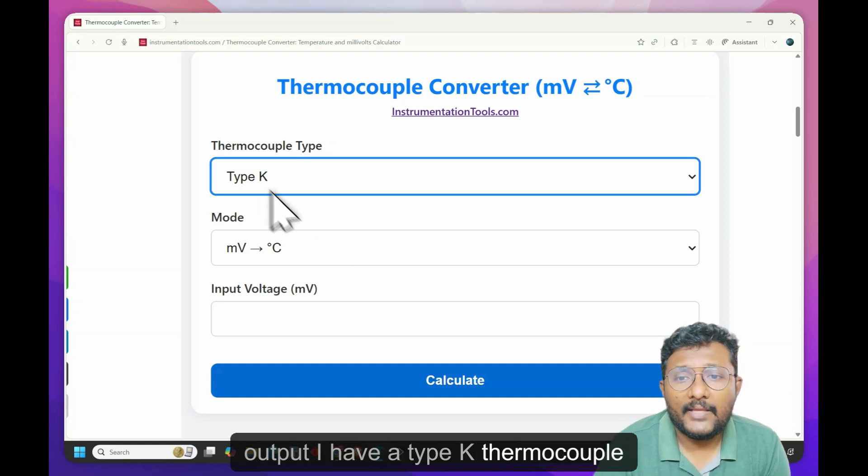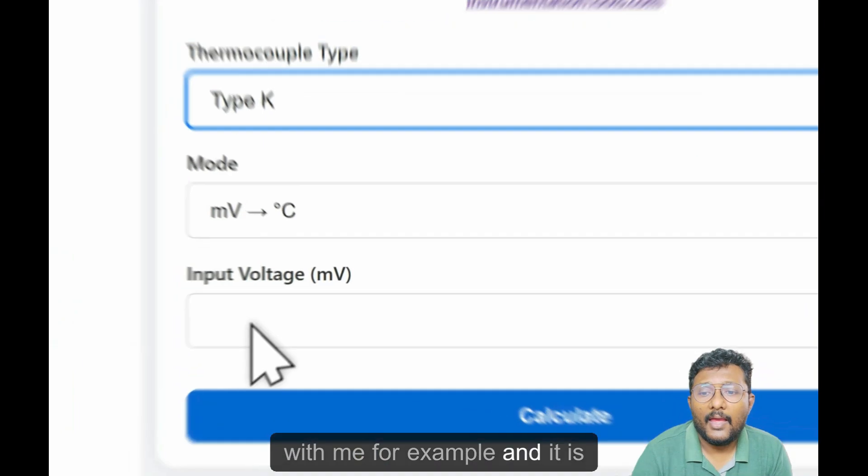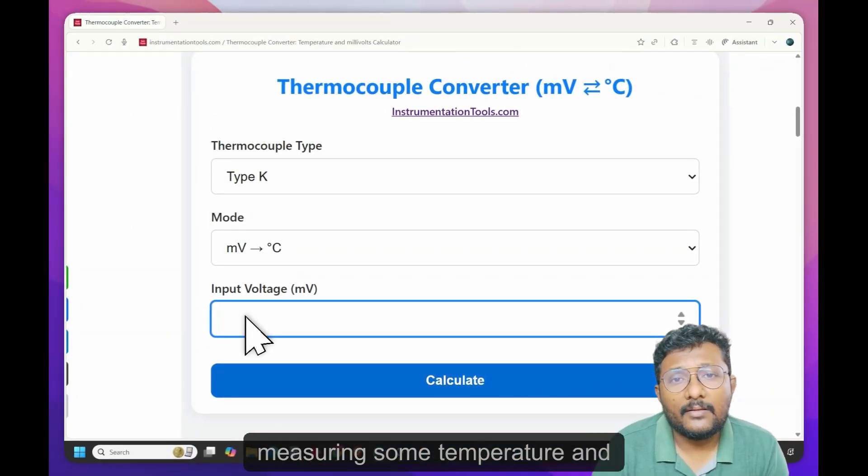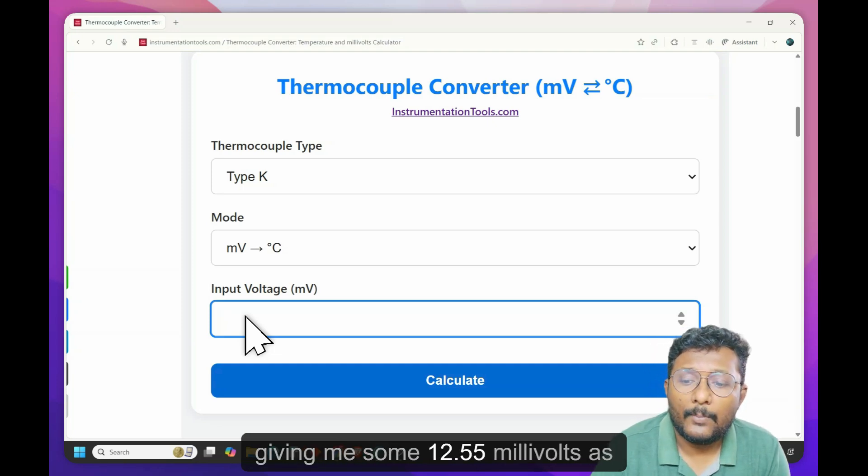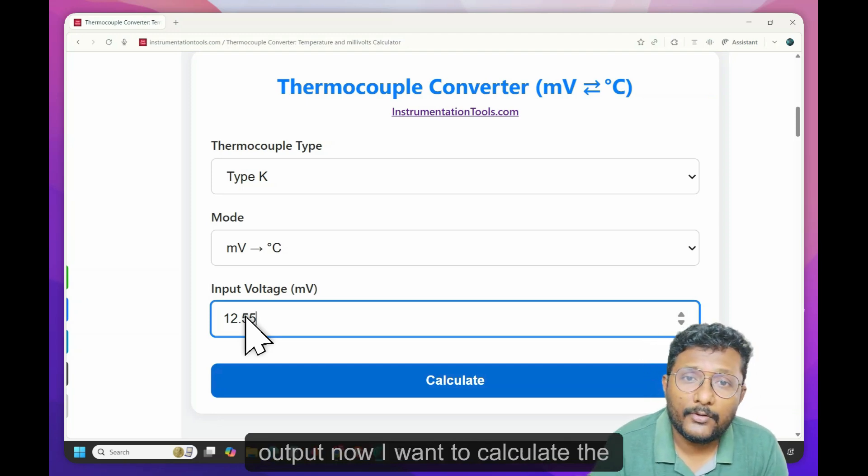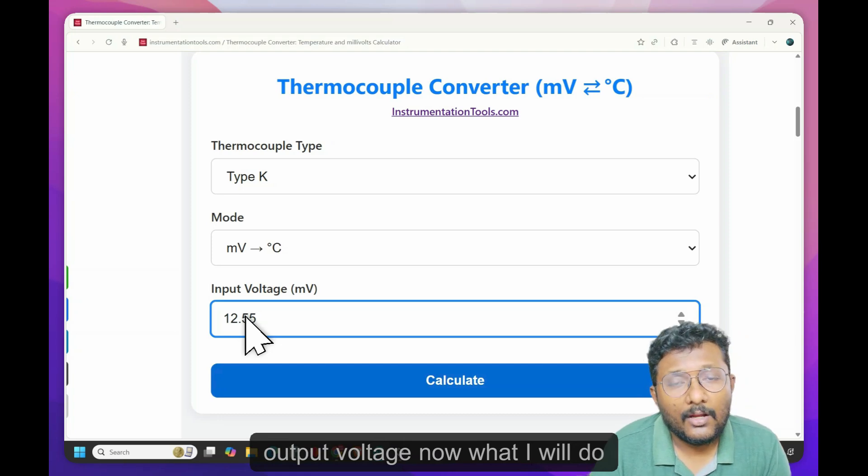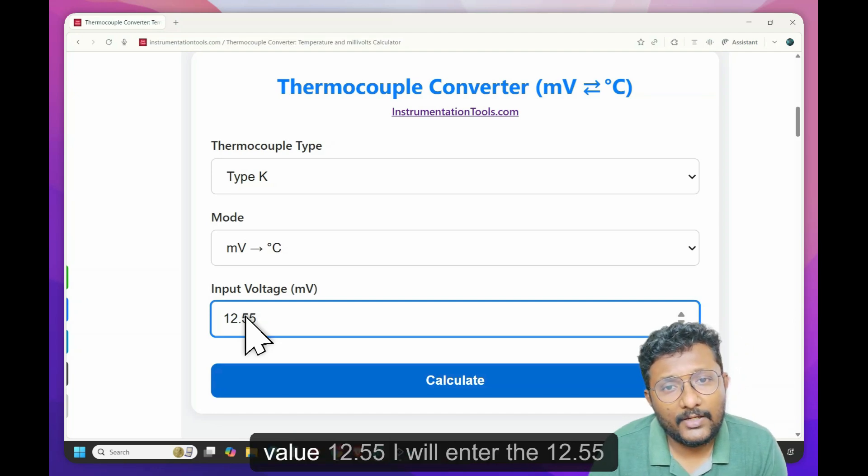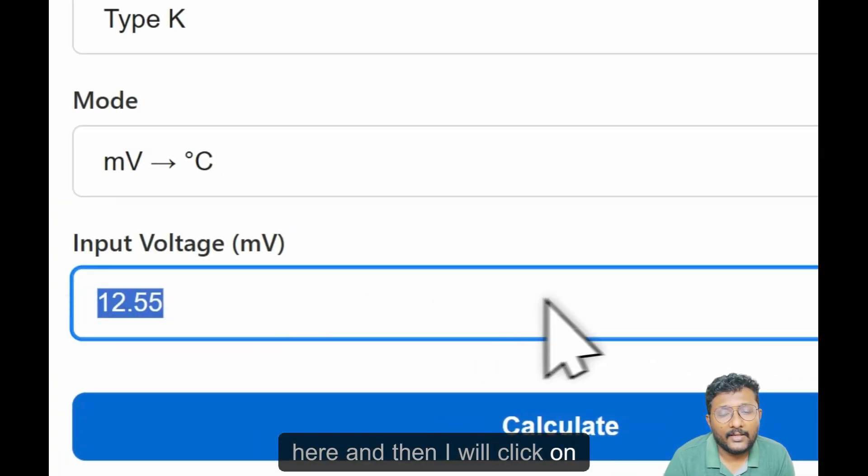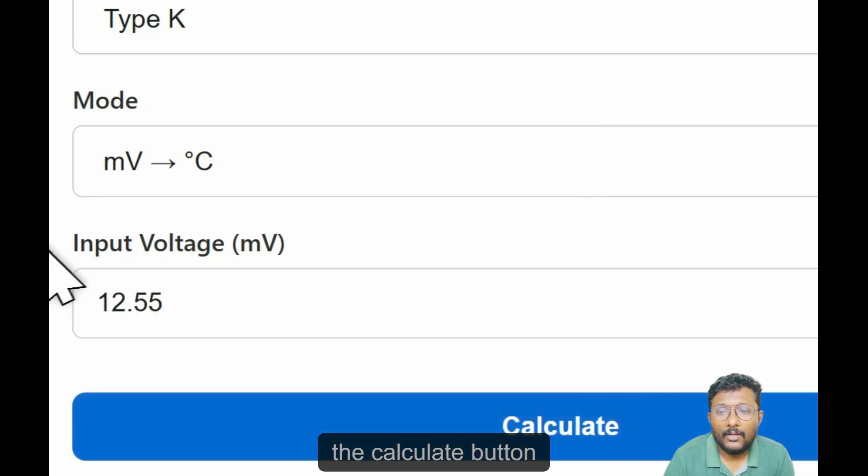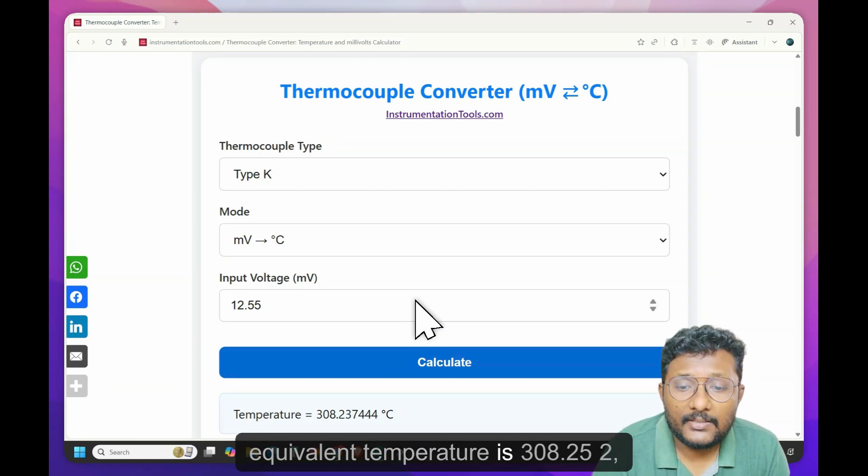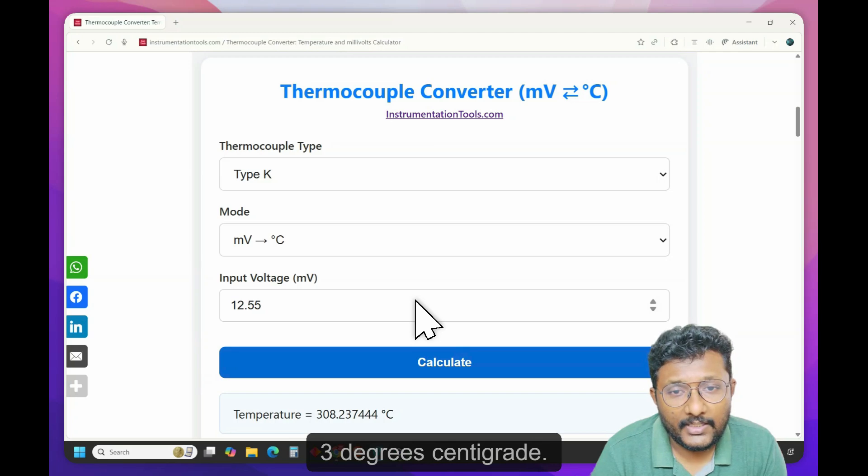I have a type K thermocouple with me for example. And it is measuring some temperature and giving me some 12.55 millivolts as output. Now I want to calculate the equivalent temperature for that output voltage. Now what I will do, I know the value, right? That voltage value 12.55. I will enter the 12.55 here and then I will click on the calculate button. Equivalent temperature is 308.23 degree centigrade.